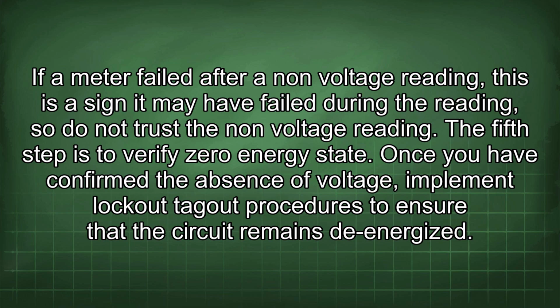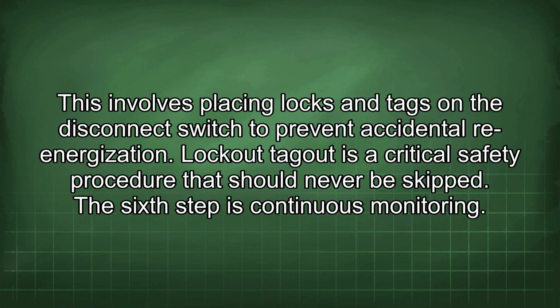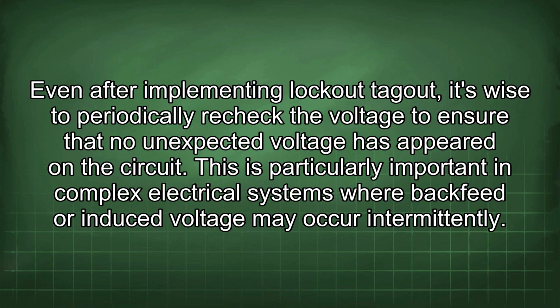The fifth step is to verify zero energy state. Once you have confirmed the absence of voltage, implement lockout-tagout procedures to ensure that the circuit remains de-energized. This involves placing locks and tags on the disconnect switch to prevent accidental re-energization. Lockout-tagout is a critical safety procedure that should never be skipped. The sixth step is continuous monitoring. Even after implementing lockout-tagout, it's wise to periodically recheck the voltage to ensure that no unexpected voltage has appeared in the circuit. This is particularly important in complex electrical systems where backfeed or induced voltage may occur intermittently.